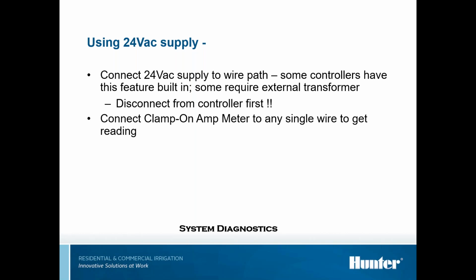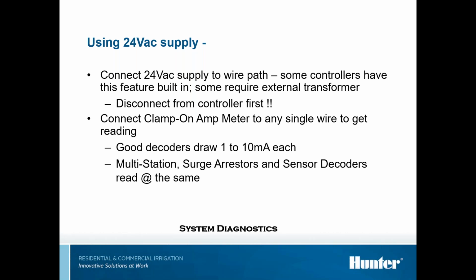Connect the clamp-on meter to any single wire to get a reading. Good decoders are going to draw typically 1 to 10 milliamps. I like to see between 7 and 10. That number is probably more accurate. Multi-station surge arresters and sensor decoders are being read also at the same time. So if you're on the wire path and you're back at the controller and you're on the main feed red or main feed blue, you're going to read every decoder that's down there: a single station, 2 station, 4 station, 6 station. So it's good to know how many decoders you're actually on that line while you're working your way down. And we'll explain that in a couple of screens.